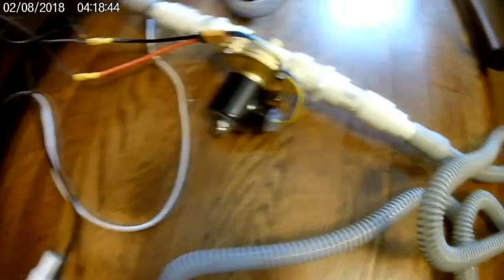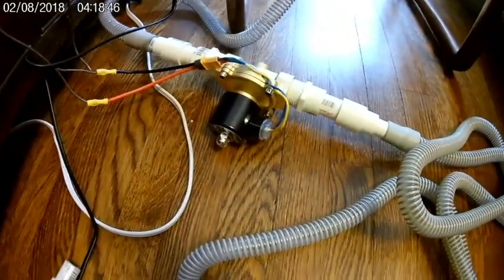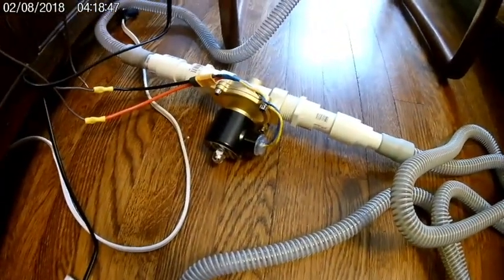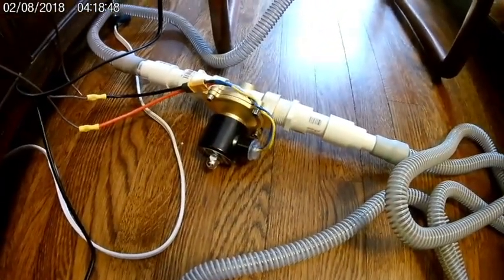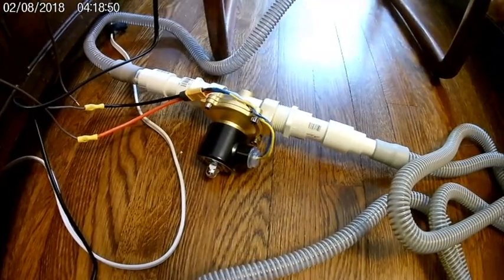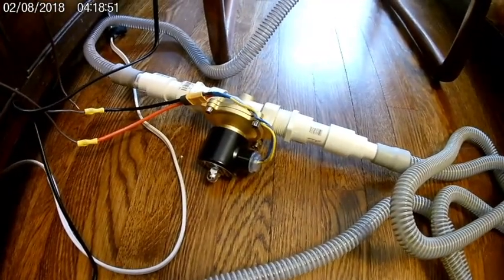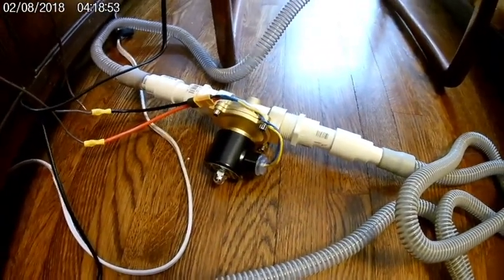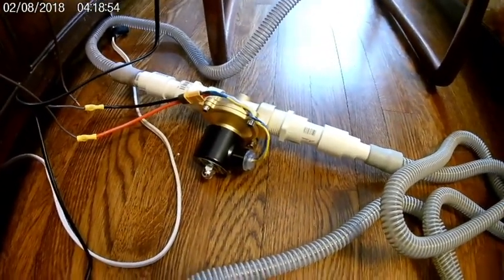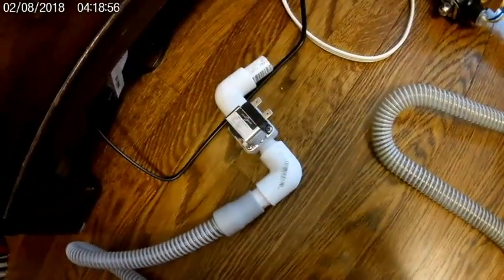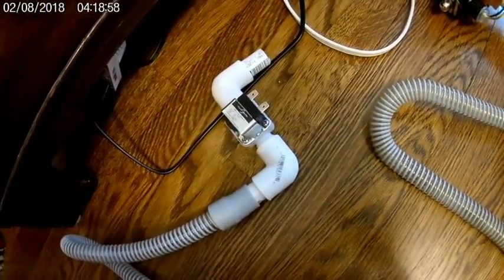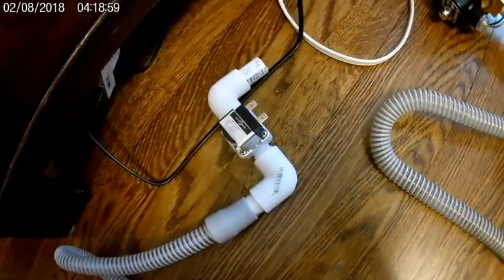I'm sure that you don't need such a big chunky valve just to do the air shut on and off. This one's made for water but it's quite effective. This one I have to change for a larger valve - that smaller one doesn't have enough air flow to make it effective. But essentially, that is how the whole system works.